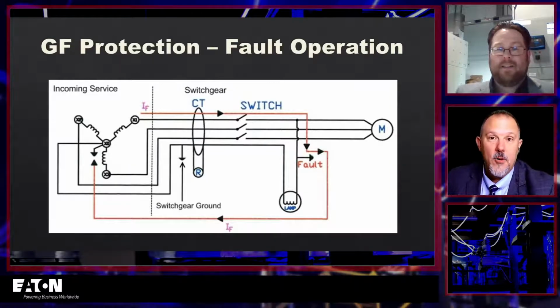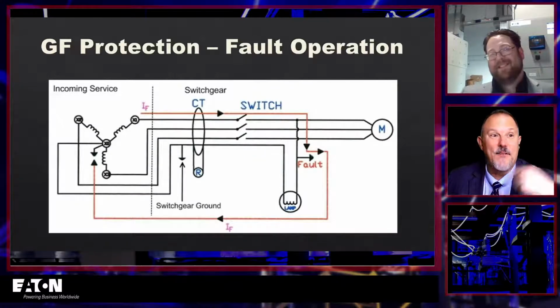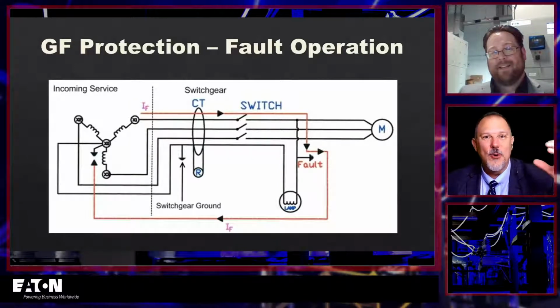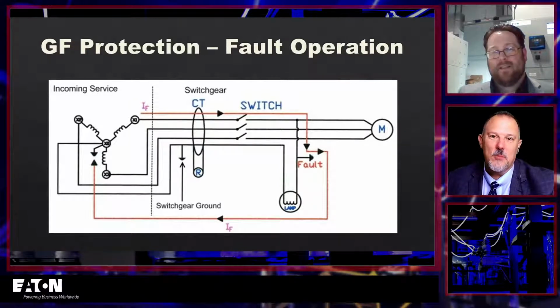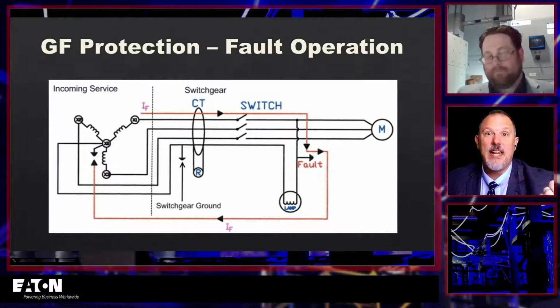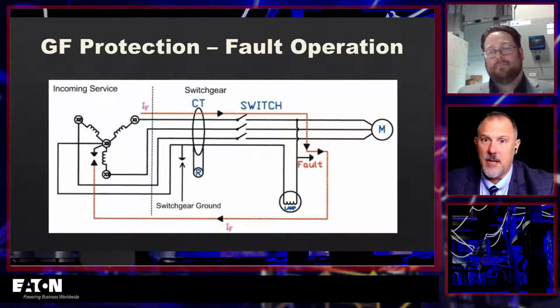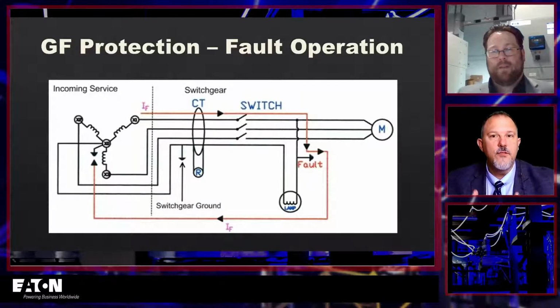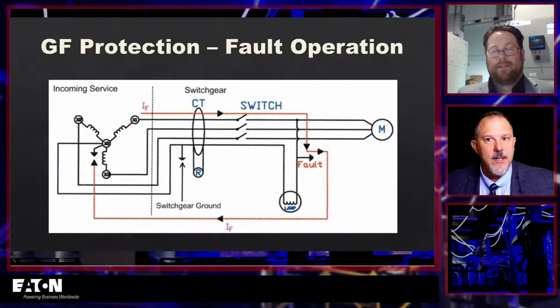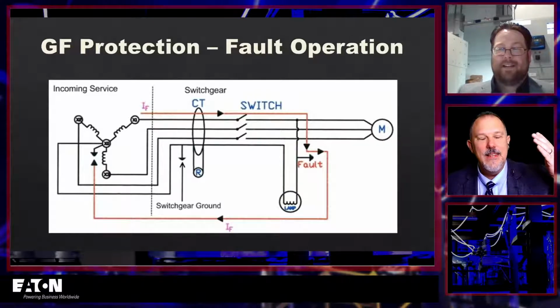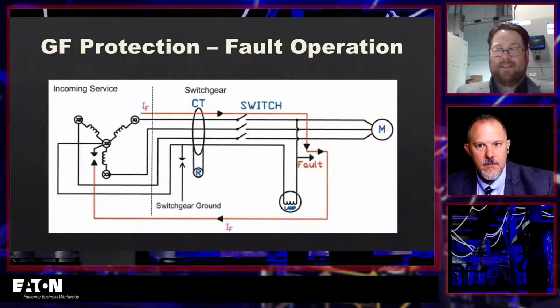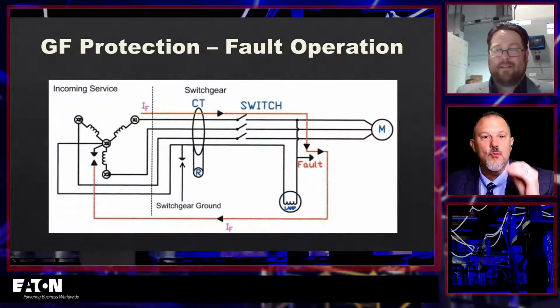And oh, by the way, the equipment grounding conductor is a bare copper conductor with no insulation. Okay, I'm going to protect the phase conductors, which have rubber or some conductor coating, which is probably going to melt well before the copper does. If I protect that from overloads, I sure as heck am going to protect my equipment grounding conductor. So then I had someone else tell me, well, Tom, you want to remove it because of shock hazards. And I said, well, grounding doesn't prevent shock because ground currents will find every way back. So I have yet to hear a logical, engineering-based, factual-based reason to increase the equipment grounding conductor size on a long run.